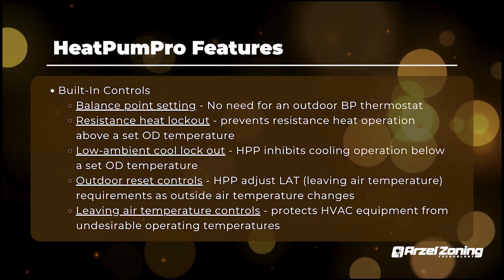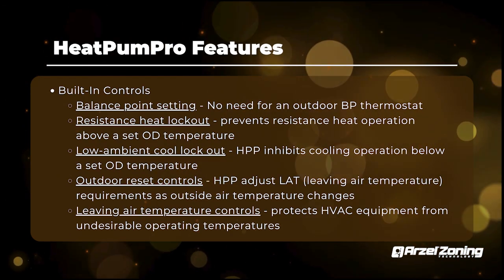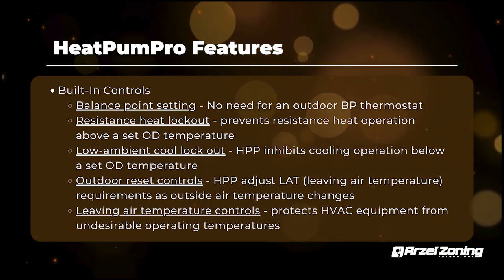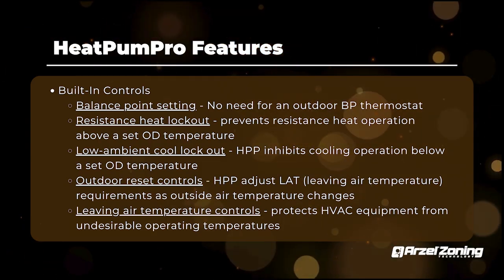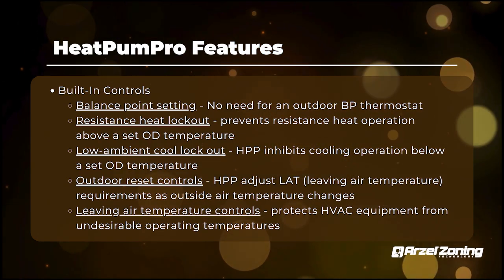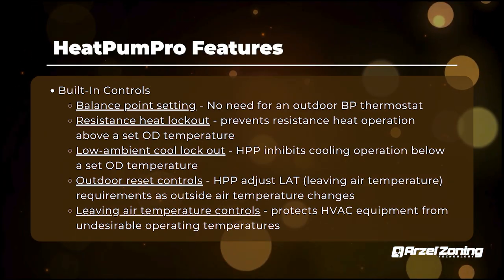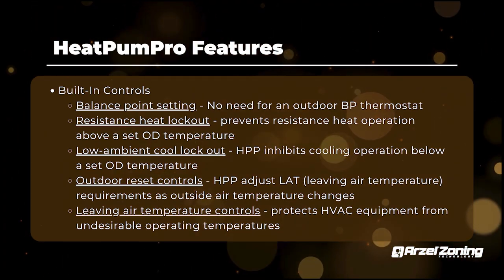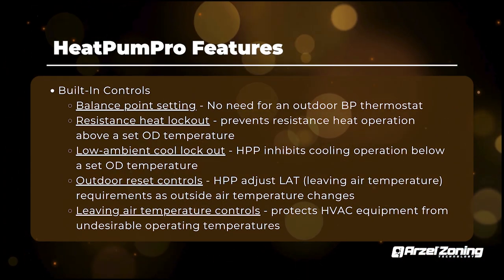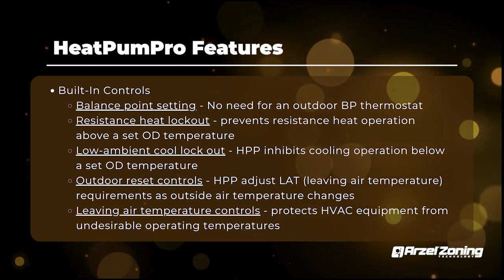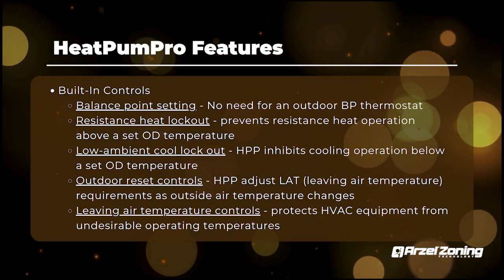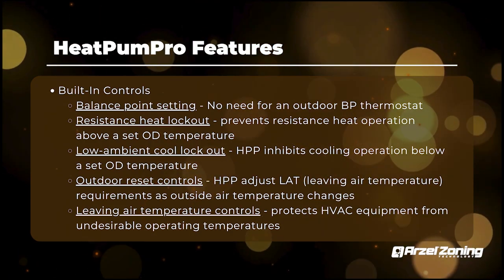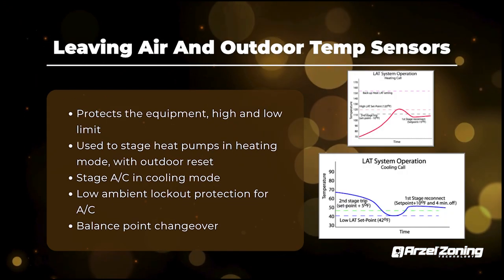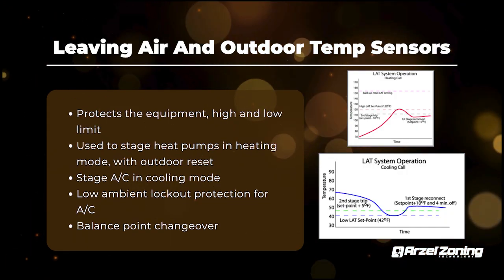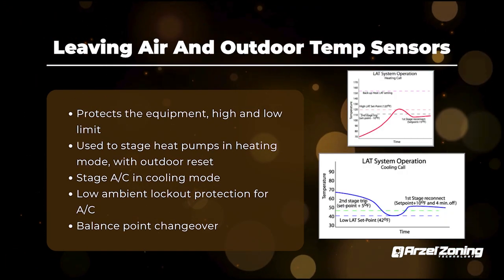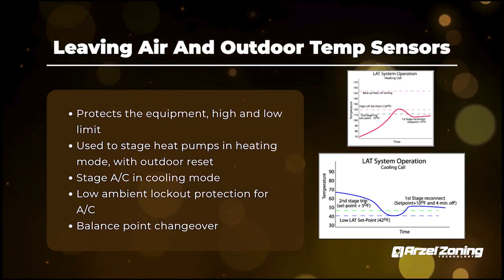So freeze protection or overheating should prevent damage to the heat exchanger or to your coil from freezing. Those are settable as well. They come preset for your sensor to be about a foot away from your coil. If you guys need to move it a little bit further than that or a little bit closer to your equipment, then you're going to need to change your leaving air temperatures just a little bit to make up for that difference. These are just your leaving air temperatures. So this is going to cover you guys on high protection and your low freeze protection on the coil.